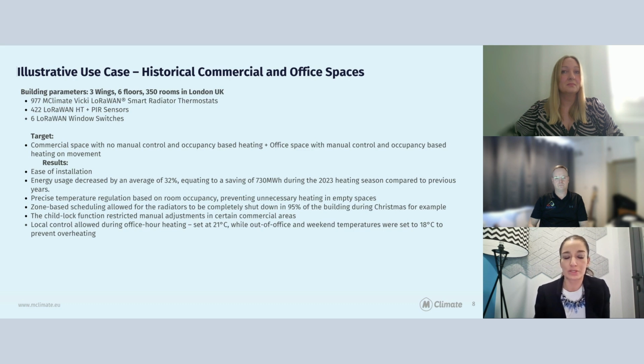With the room-by-room thermostat that we introduced, we could get precise data for every single room. That precise temperature regulation, which we could adjust on the room occupancy-based system, prevented unnecessary heating of a lot of empty spaces, in particular office spaces and gallery spaces in that particular building. So we use the child lock function that I didn't mention before. The child lock is just a manual lock that restricts people from changing the settings. This is something that we introduce in all the commercial spaces, but we allow some feedback from people in their office spaces so that they're not locked from changing the setup of 21 degrees to something higher.